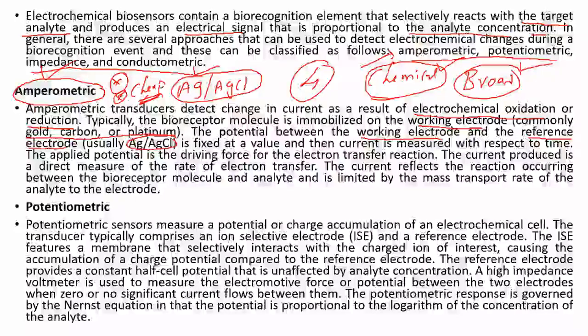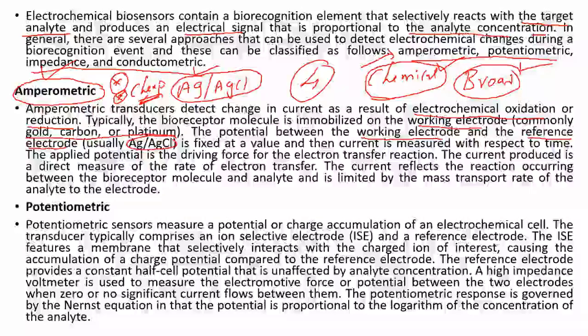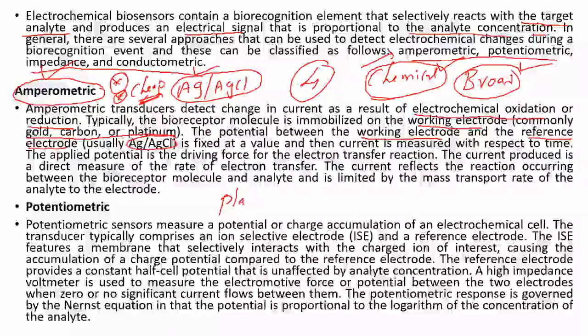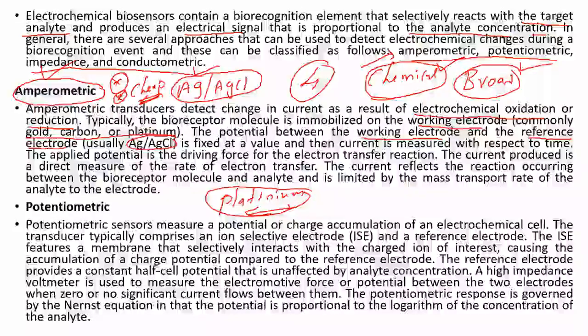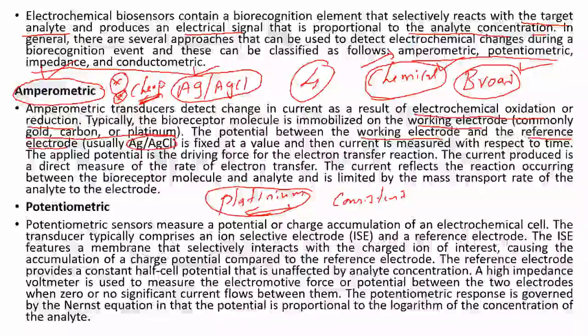Ag/AgCl electrodes are preferred because they are pretty cheap to install and maintain, and produce minimal noise in biomedical signals. Other electrodes like platinum exist, but the Ag/AgCl oxidation-reduction process is very consistent with low noise.